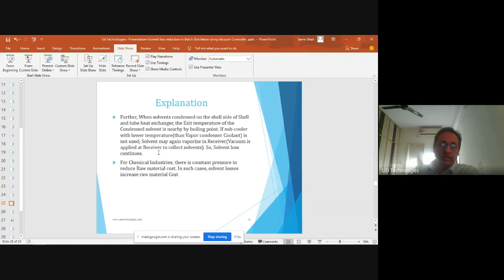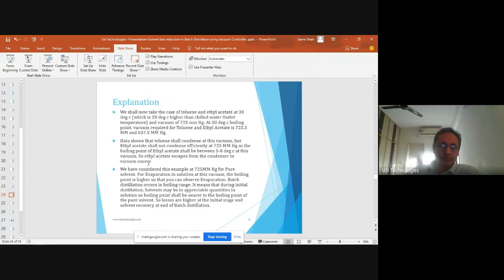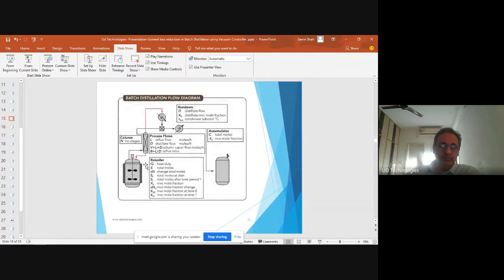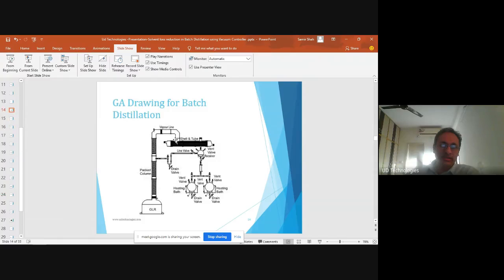I just explained, as we discussed in the drawing, that we are using shell side condensation. When solvents condense on the shell side of a shell and tube heat exchanger, the exit temperature of the condensed solvent is near the boiling point. I will show you in the drawing. Yeah, this is shell side condensation.